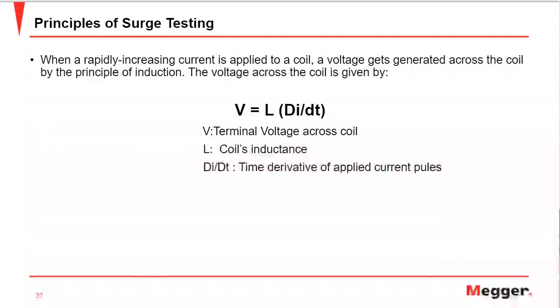What are the principles? I'll read this aloud. When a rapidly increasing current is applied to a coil, a voltage gets generated across the coil by the principle of induction, and that voltage is given by V = L di/dt. V stands for the terminal voltage, L stands for the coil inductance, and di/dt stands for the change in current with respect to time. The terminal voltage V at the leads of that coil is the sum of the induced voltages created between individual loops in that coil. If the insulation that separates the coil is weak, and the induced voltage is higher than the dielectric strength of that weak insulation, an arc will form between those coils.